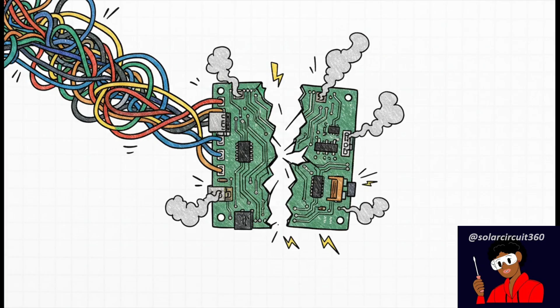If you wire these out of order, say connecting a higher voltage point before the lower voltage reference point, your BMS suddenly gets hit with impossible, excessive, or even negative voltages right on its delicate sensing inputs. The result: it permanently damages its own internal electronics instantly. Literally instantly. It's like immediately setting a $100 bill on fire. One wrong wire, and your very expensive BMS is now just a paperweight.